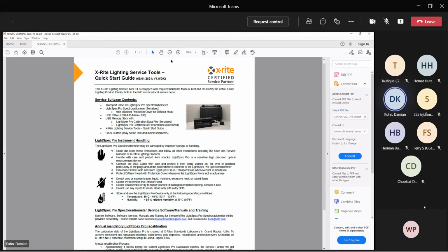What you have included in the toolkit is, of course, the USB cable to connect it to your computer. Along with it, what we decided on for the new solution is that there is a memory stick included in the case, and we intend to put the calibration data file for the instrument as well as the certificate for the Lightspex Pro instrument on that memory stick, so that you should have everything without asking us to provide the calibration file as happened in the past on the old Lightspex instrument. Whenever you return your Lightspex Pro instrument to us in future for recalibration, ensure that you include that memory stick, and then once you get the device back from us after recalibration, you should directly have everything you need on that memory stick.